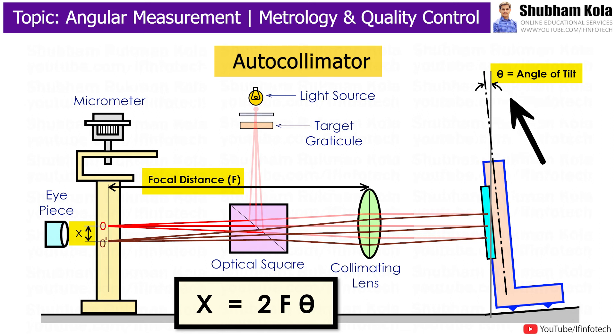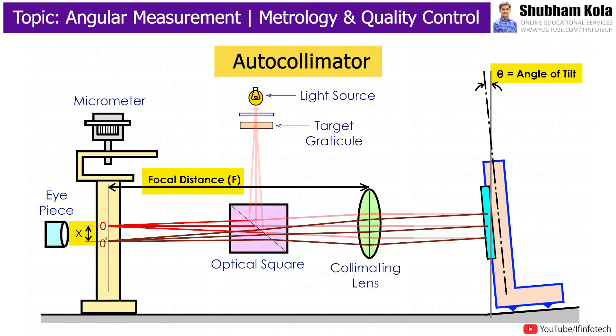In this way, we can measure the angle of tilt with the help of the Autocollimator. Most Attocholimeters are calibrated so that there is no need to convert the measured distance into an angle of inclination. This conversion is done within the Autocollimator itself, and the angle of inclination can be read directly.